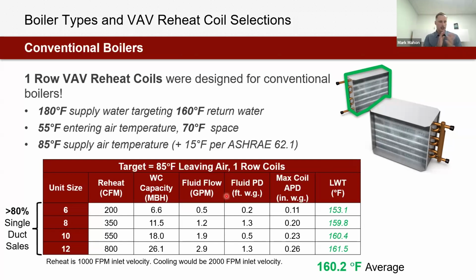I'm also going to pause here because this is a really good question that kind of relates to this table from Jonathan in the chat. So thank you, Jonathan. And his question is, in regards to airflow measurement and control, can Price single duct VAVs provide constant airflow at 20% of design airflow? So 20% of design airflow kind of existing at 360 to 400 feet per minute, if our maximum supply airflow rate is 1,800 to 2,000 feet per minute. And how is that influenced by different product options?